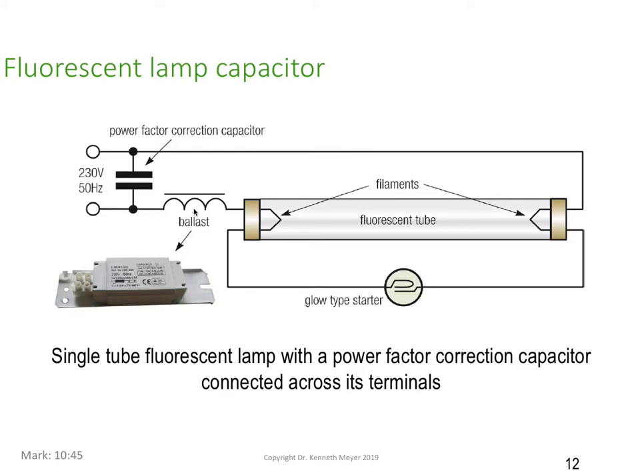So when you're buying a high power factor corrected fitting, it has a capacitor fitted in parallel across, and the inductance of the ballast is being offset by the reactance of the capacitor. So the two reactors here, one at plus 90 degrees, the other one at minus 90 degrees, they're 180 degrees apart. So from the outside, from the supply side, it looks like the lamp has a power factor of 1 or very, very close to 1, normally about 0.95.